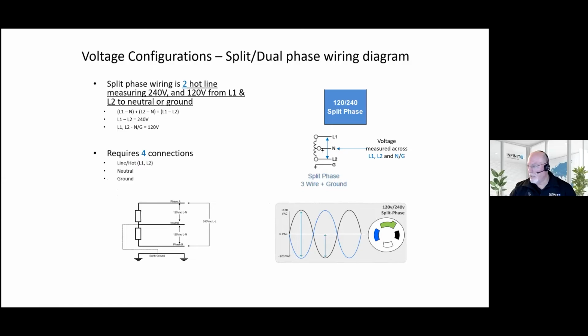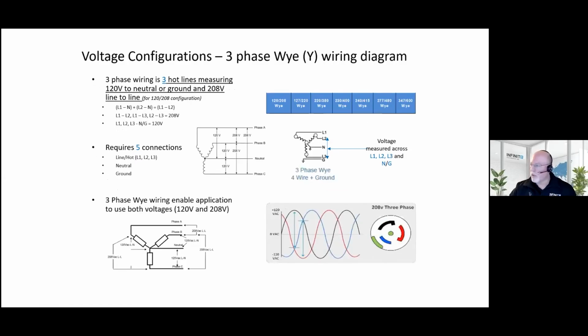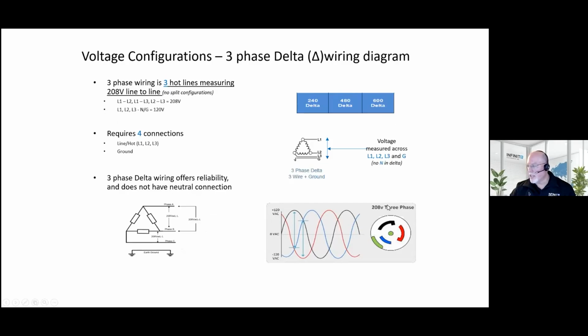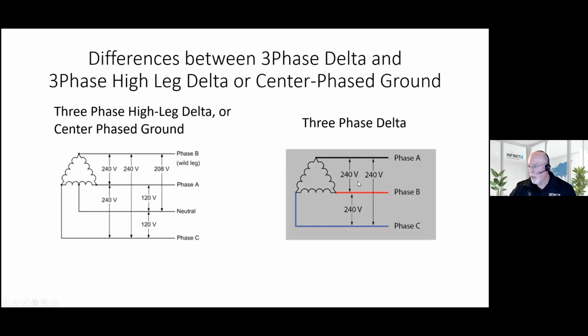And these are just examples for future reference if you ever want them. But here's a 3-phase Y. It's spelled this way, and because of this, these are the transformer windings that derive a 3-phase Y scenario. It could be 120/208, 277/480, and so on. This is a delta, which doesn't have a neutral, shaped like a delta. So that's pretty cool. And this is a very old and unusual configuration called a high leg delta, which does have a neutral. Mostly in the south, but they're out there.